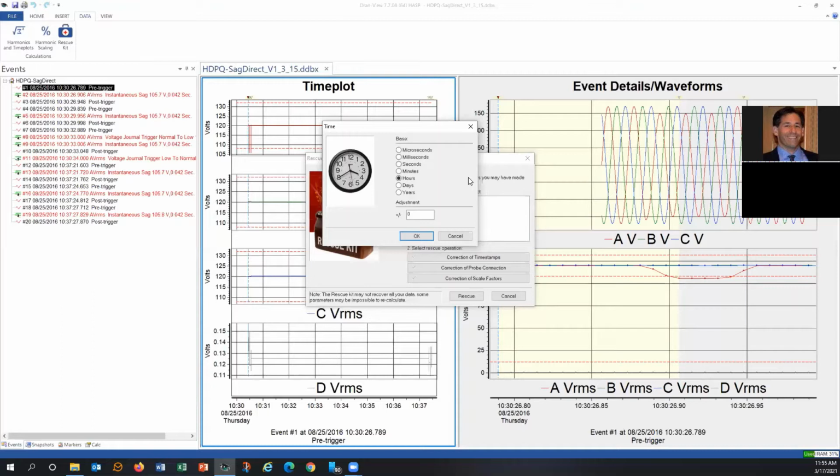Another option for the time calculations is if you have multiple instruments. Quite frequently, multiple instruments are doing measurements, so oftentimes you want to align the time of those instruments. If you know you have an event on an instrument, you know one instrument has the time, you can adjust the time of another instrument, in microseconds, milliseconds, or seconds, to line them up on top of each other.